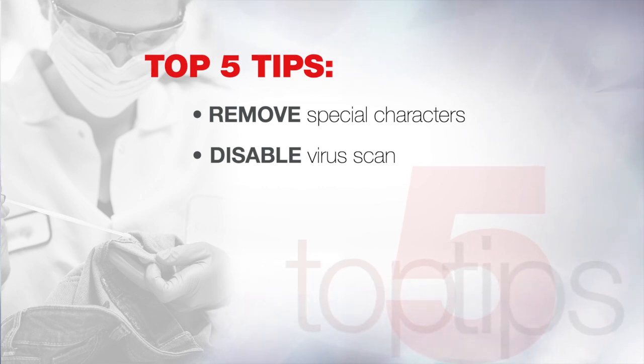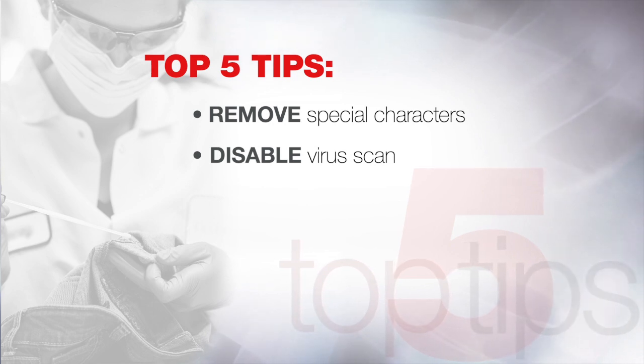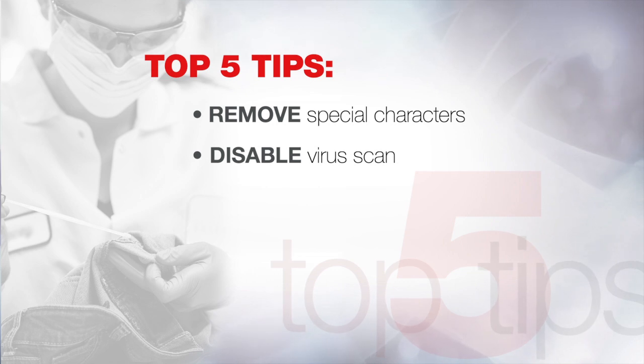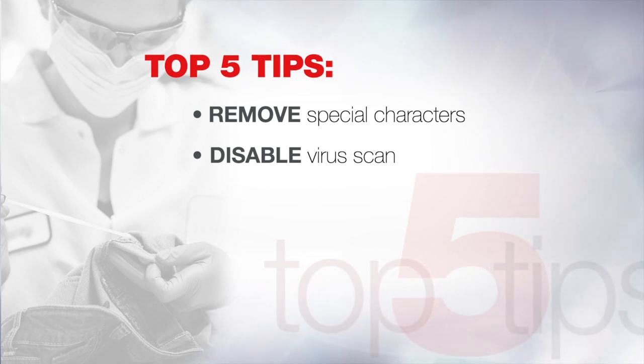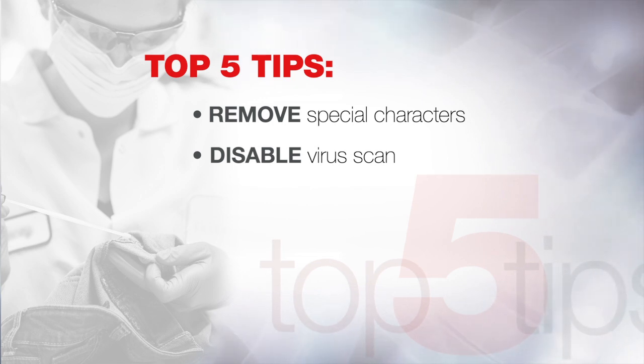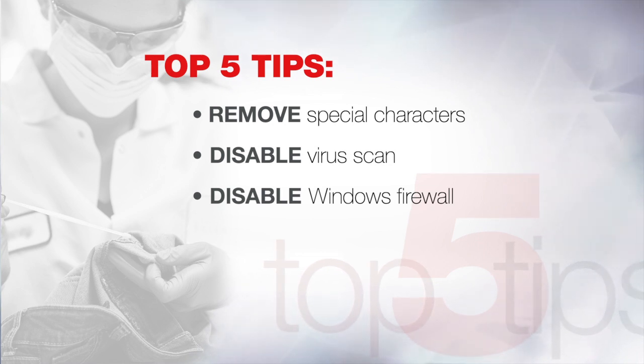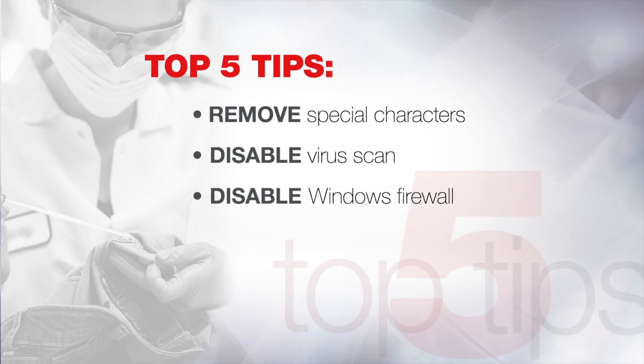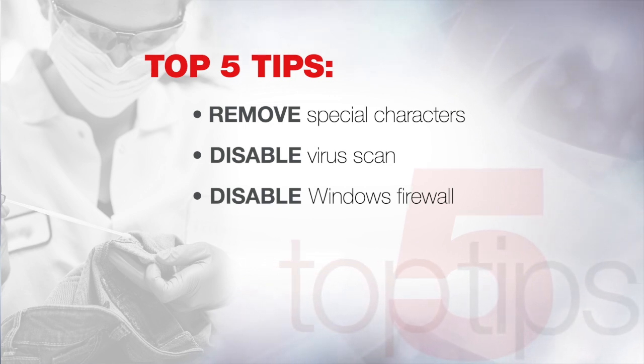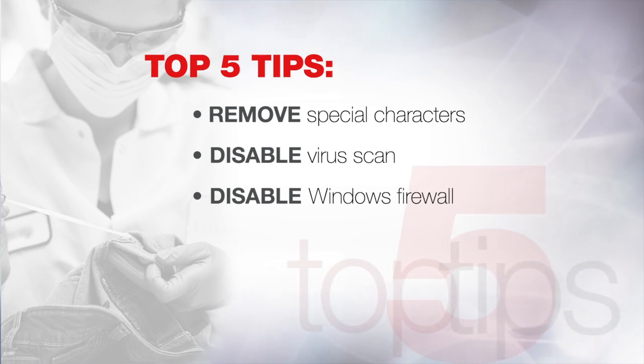Number two — always disable virus scan for installation. Whether you have a separate application or the built-in Windows virus scan and threat detection, you want to disable that for installation, as it will definitely halt an installation of GeneMapper IDX software. Number three — very similar to number two — disable your Windows firewall for the purposes of installation. It's wanting to prevent major changes to the software and connections to it. Even though you're installing on your laptop and it's not really connecting to any other computer, the software still wants the ability to connect, so disable that Windows firewall.